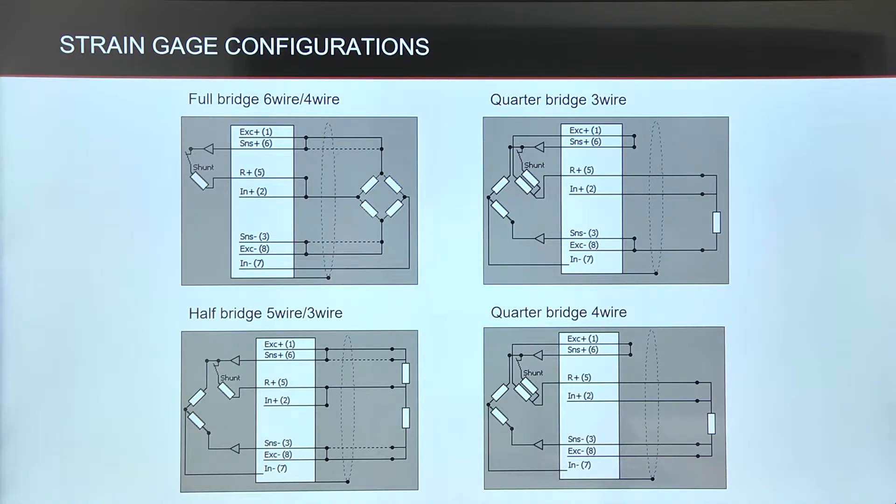Precise bridge completion resistors are integrated into DeweSoft hardware to be able to measure in half or quarter bridge mode. If for whatever reason sense lines are not connected directly at sensor site, lead wire resistance must be taken into account to avoid offset and gain error.